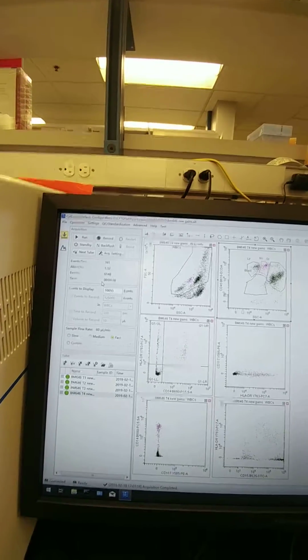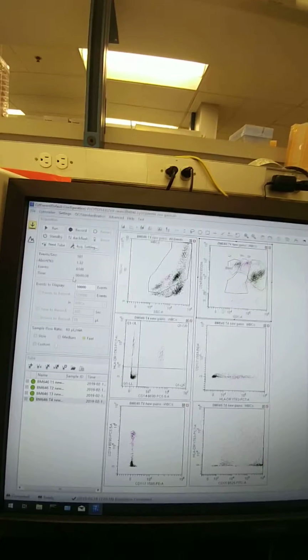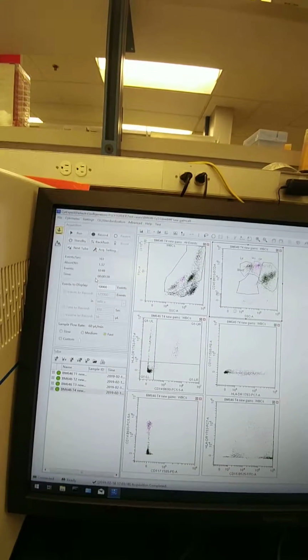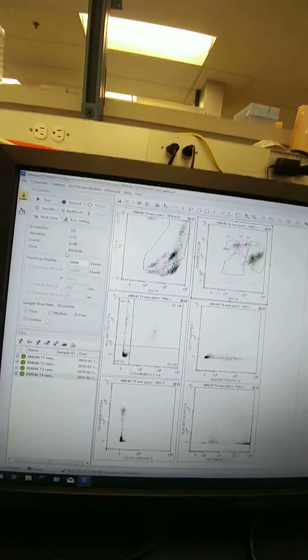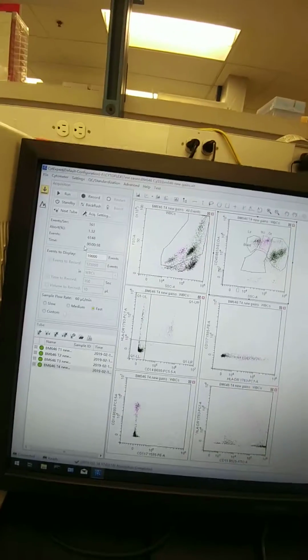Duplicate the tubes and try changing the settings at different increments of 10 or 20 or 50. Just try a couple different ones, collect the data, save it, upload it into the portal, or make it available so that we can look at it, and then we can analyze it with you as well and let you know what you should be changing and saving those new gains to.